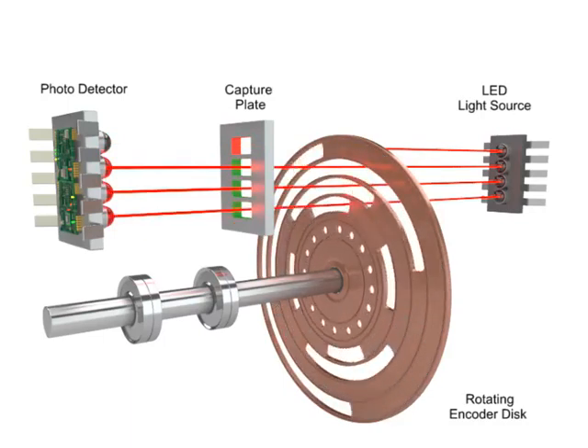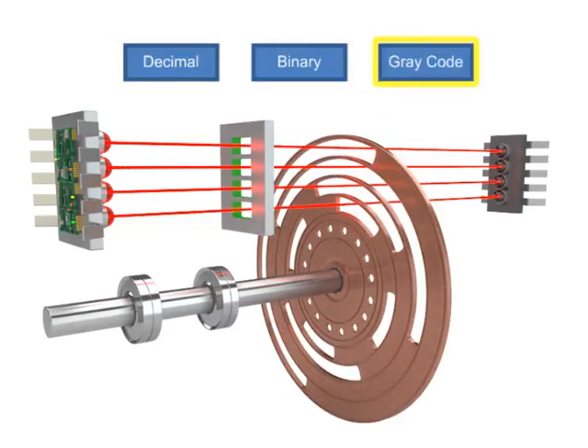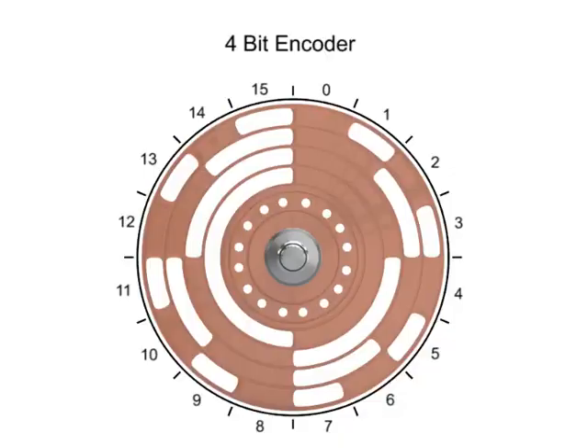The most common types of numerical encoding are decimal, binary, and gray code. In a four-bit encoder there are 16 unique combinations or numeric codes every 22.5 degrees.